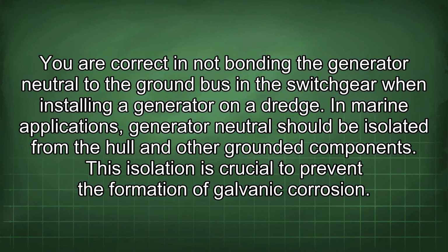You are correct in not bonding the generator neutral to the ground bus in the switchgear when installing a generator on a dredge. In marine applications, generator neutral should be isolated from the hull and other grounded components. This isolation is crucial to prevent the formation of galvanic corrosion.